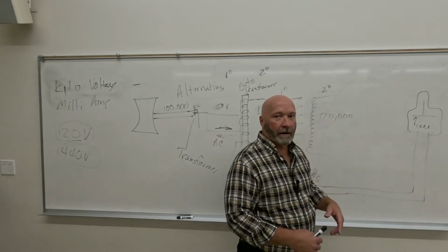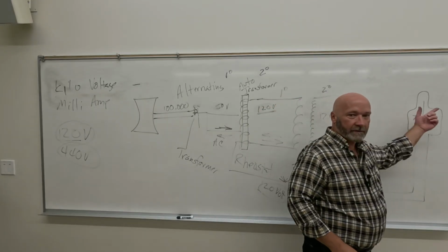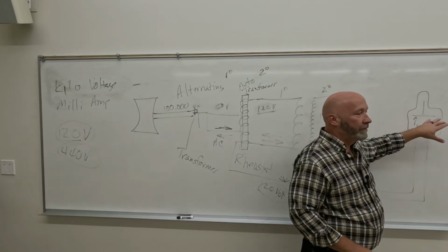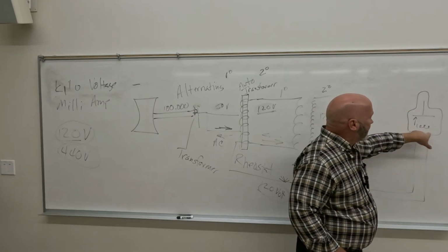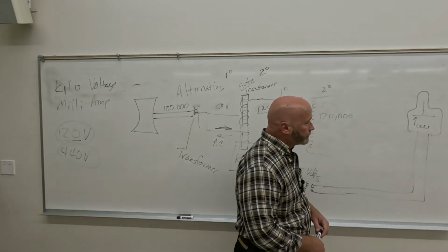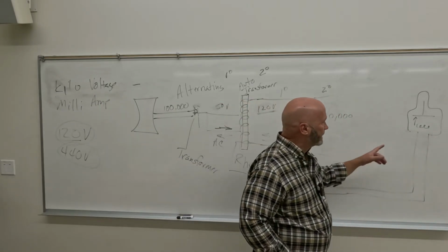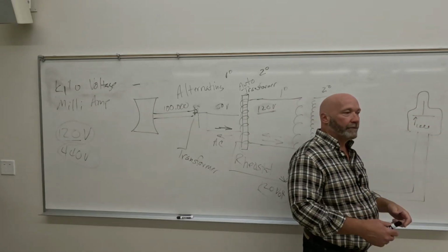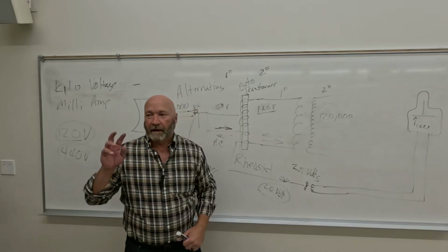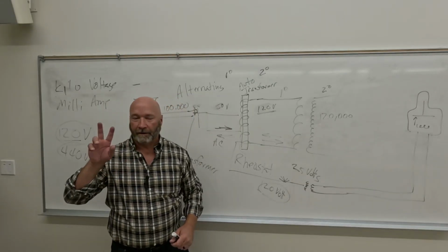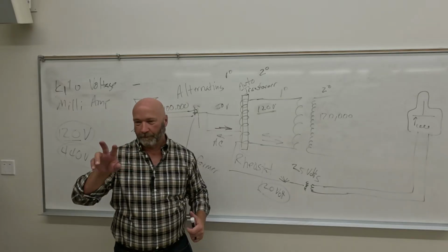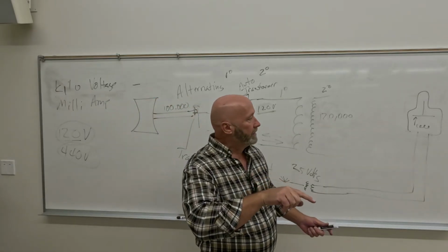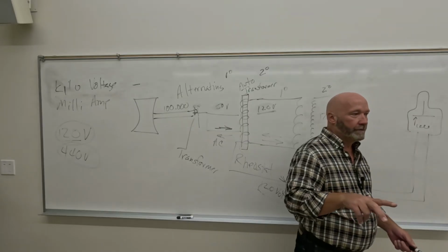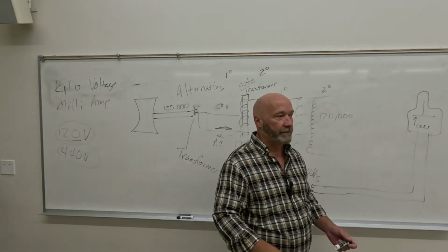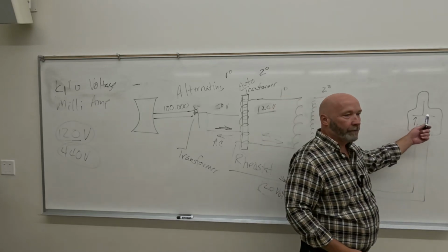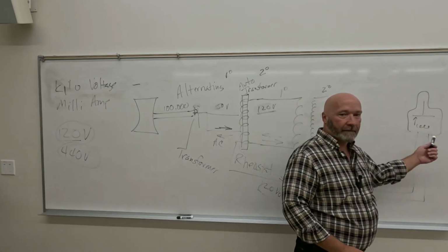So when they say rotor up, that's what's happening. What you're hearing is that thing starting to spin. Okay, 1 second later, you're ready to shoot. So it's spinning that and it's heating that up. Now you're ready to go. But you're working off a low voltage at that point to keep the electrons from jumping across the tube until you're ready. So most X-ray machines have a control panel with two buttons, and really probably three. One is a prep button, and that's your rotor button, and the other is the exposure. You can make an X-ray just by pushing the exposure button, but again, it's not going to give you an exposure for 1 second, to give all this time to go.